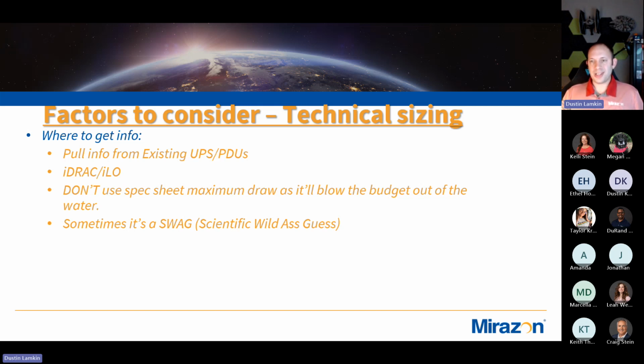If you go by the spec sheet, those numbers are all built off the maximum draw, so we definitely don't want to use that. But we do need to keep it in mind when we build out UPSs and PDUs, because in a startup situation, if you start everything at once, it'll be close to that maximum draw while all the fans are spinning up and everything is turning on. We need to be cognizant of that so we can fire things up properly and not overload our systems when we're starting back up.